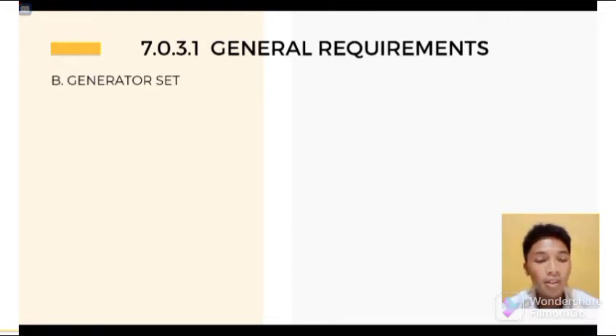For a generator set driven by a prime mover acceptable to the authority having jurisdiction and sized in accordance with 7.0.1.5, means shall be provided for automatically starting the prime mover on failure of the normal service, and for automatic transfer and operation of all required electrical circuits. A time delay feature permitting a 15-minute setting shall be provided to avoid retransfer in case of short-time re-establishment of the normal source.